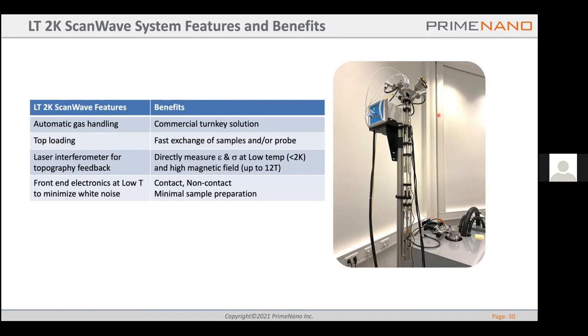You can see that it's a top loading one. That means you can just take the sample and probe out to do a quick sample exchange. It can directly measure conductivity and permittivity below 2 Kelvin, and it's also compatible with magnetic fields up to 12 Tesla. You can do contact measurement and non-contact measurement, and the sample preparation is pretty straightforward.